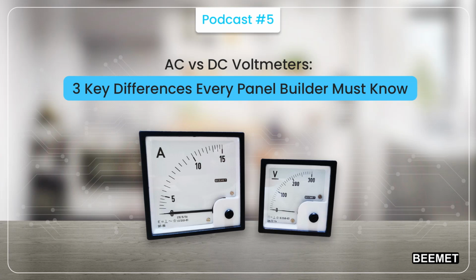The first step is to verify the voltage range and determine whether the system uses AC or DC. Next, it is important to check the accuracy class of the meter and ensure it is compatible with other components in the control panel. You should also make sure that the meter meets system requirements in terms of isolation and proper rating. Another critical step is to test the voltmeter under actual load conditions during panel design. Relying only on catalog specifications may not reflect how the meter performs in real-world scenarios. Making the right selection at this stage helps prevent operational issues later.